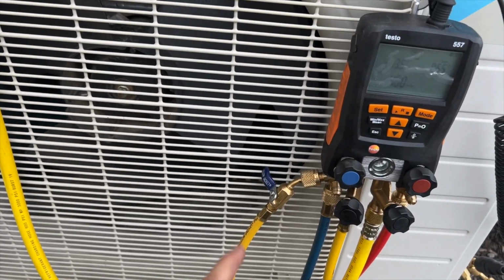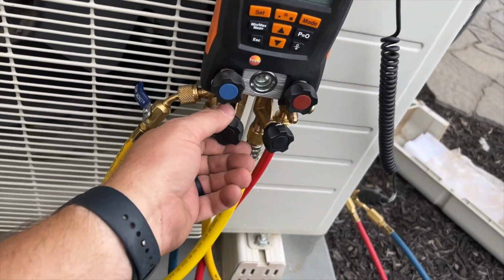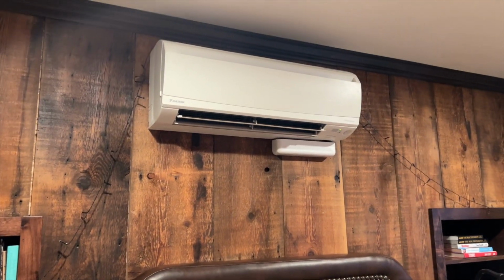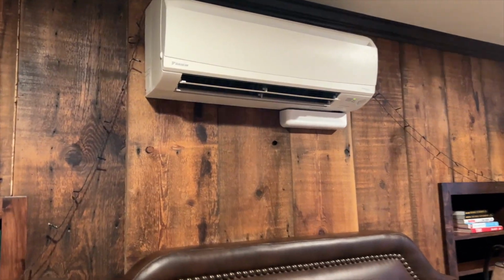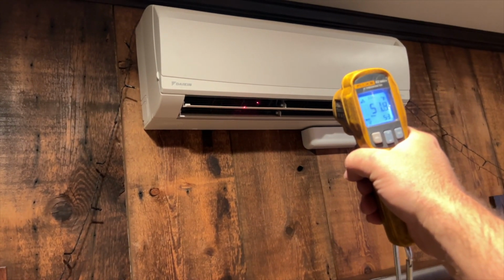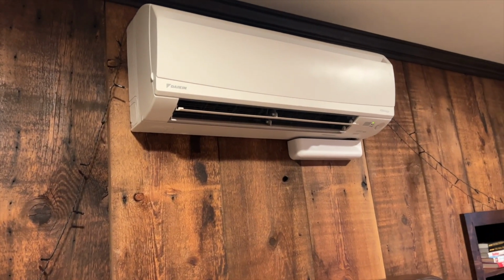Alright, we are at 480 microns, so we're going to go ahead and turn this off and charge it up. Okay, so we got her all put back together - everything's working fine, the blower's running normally, and it's actually cooling. So looks like we're good to go.